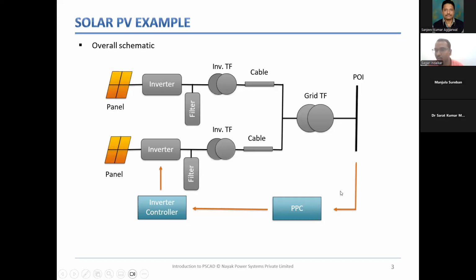So PPC will take measurements from POI, and it will ask for set points, that is the operating point of the plant, from the operator. And based on these inputs, it will take certain decisions. Now that decision is basically the P and Q order, active and reactive power order from the PPC. And that will obviously go to your inverter controller. So the inverter controller will take the P and Q order from your PPC, and it will correspondingly generate individual outputs from the converters. There will be certain losses, and ultimately the power will reach the POI, it will be measured, and this forms a loop. It forms a closed loop. Now, this is how a typical renewable energy plant functions. So from this, what we learned is, if I want to look at the dynamic behavior of the plant, it is very important to study the response of the PPC, right?